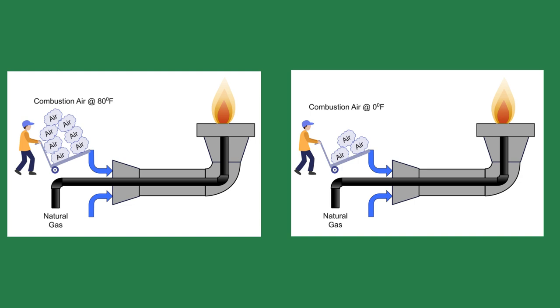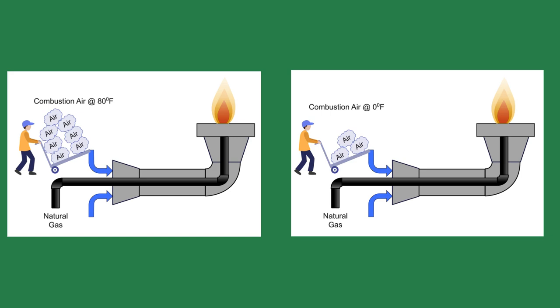When I'm adjusting the air to fuel ratio on a boiler or burner with combustion air vented to the outside, I sacrifice efficiency by a percent or two to be sure the boiler is operating with enough combustion air when it's warmer. That's what I suggested to this contractor.